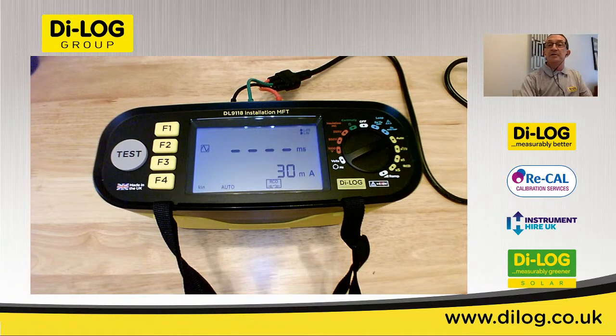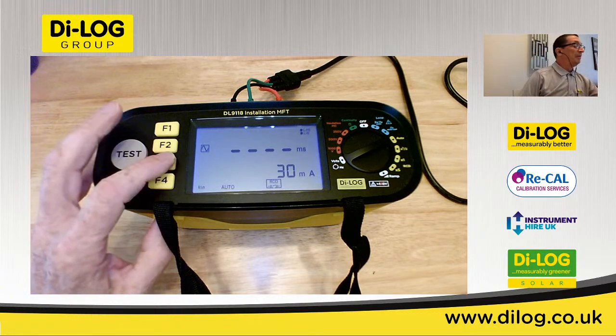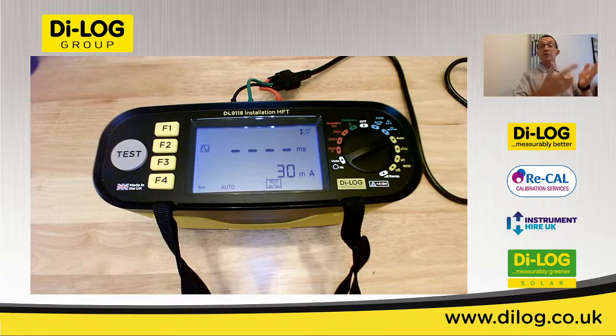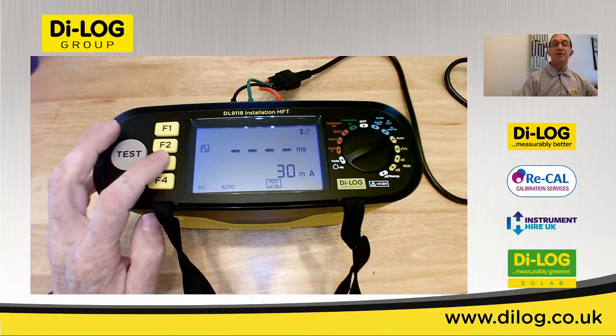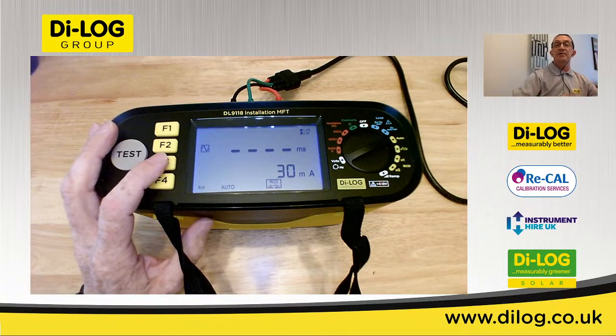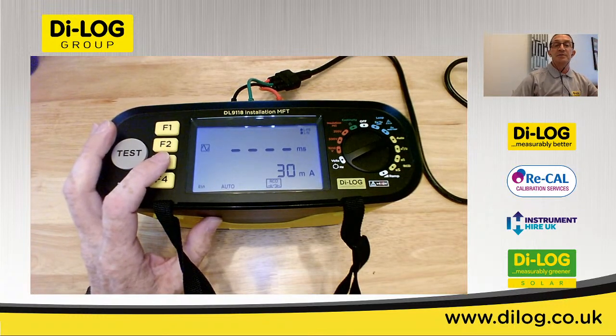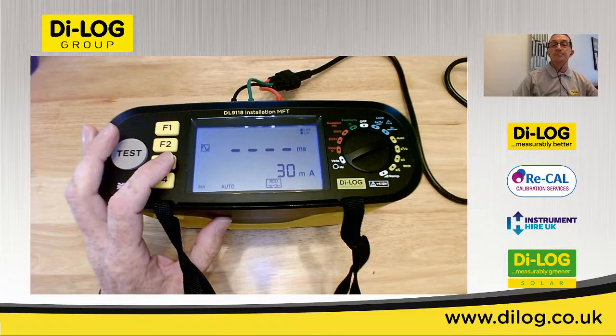So it'll carry out the half times test on the 0 phase and the 180. It'll then move automatically to the times 1 on the 0 and 180, and the times 5 on the 0 and 180 as well. And once that test's all complete, function 3 would cycle through all the various tests that we've got there, all 6 tests. Keep pressing function 3 and it'll continue to display those on the tester's display, so you can take time to write those down.